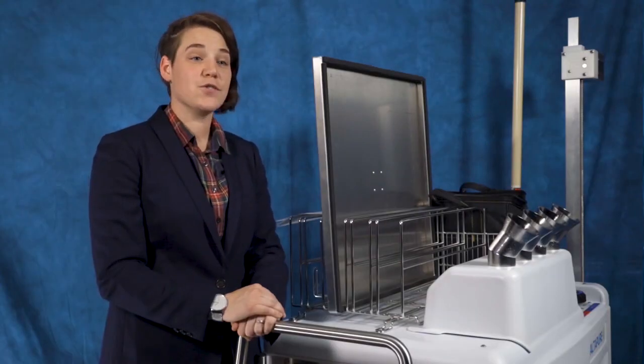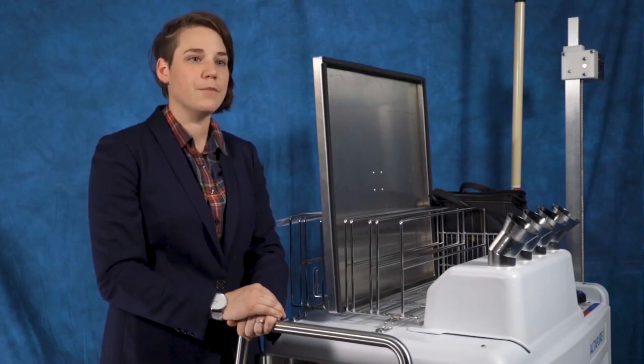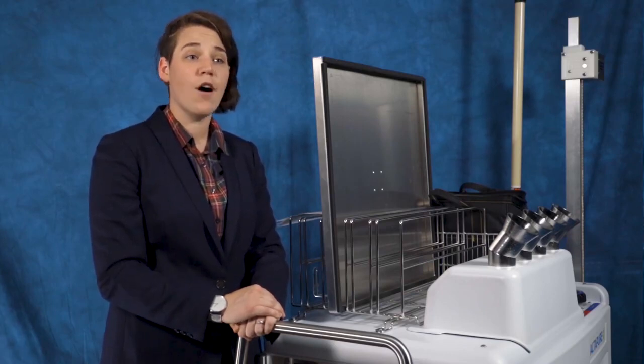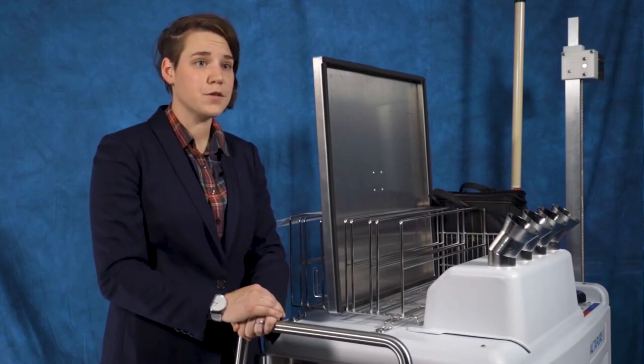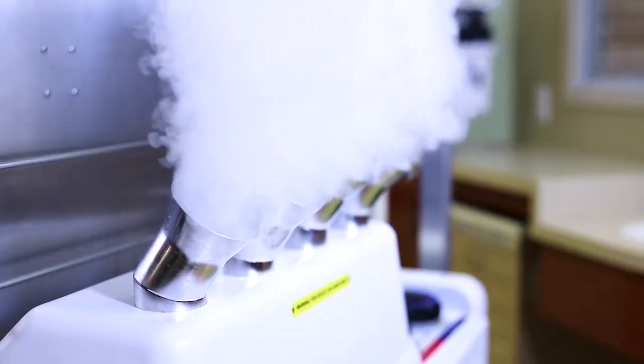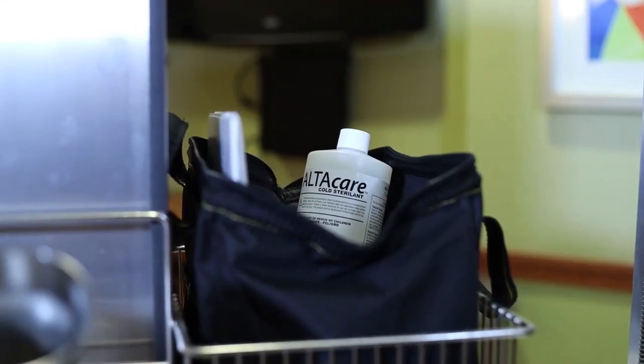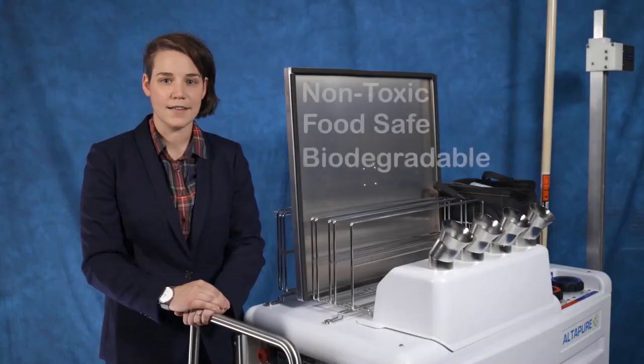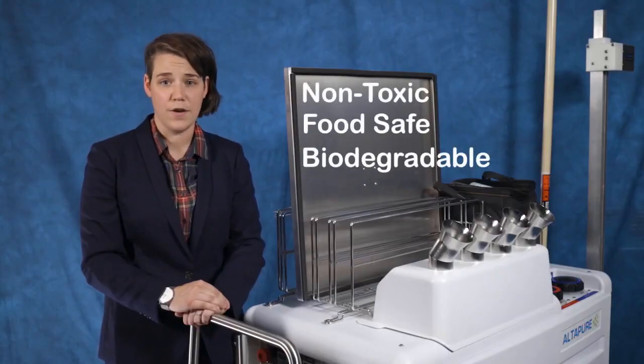The purpose of Altapure is total room high-level disinfection, typically the last step in an overall cleaning process. The system eliminates all pathogens, including spores, from all exposed surfaces in the room. The machine emits a fine aerosol of PAA, or peroxyacetic acid, that's comprised of hydrogen peroxide and acetic acid. The chemistry is non-toxic, food-safe, and biodegradable.